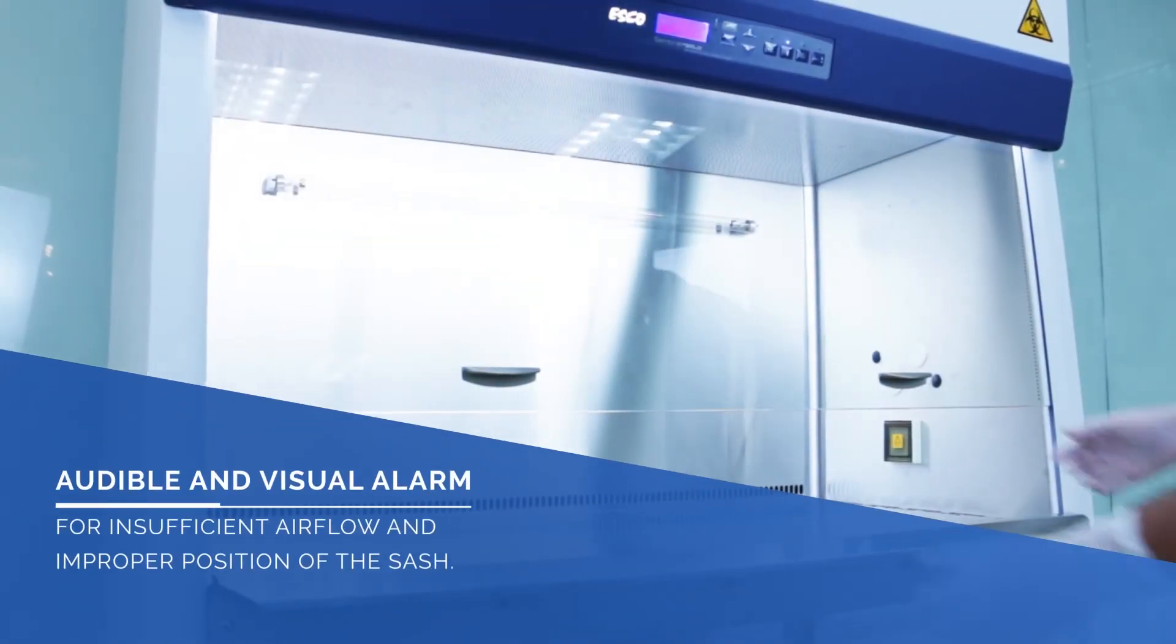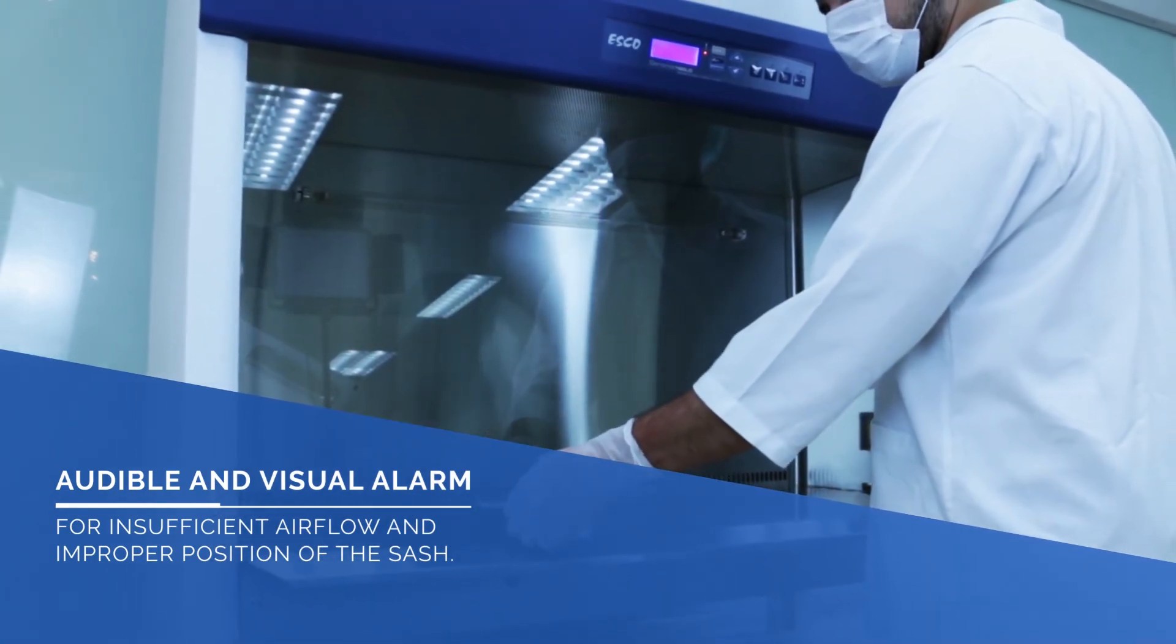There are audible and visual alarms in case of insufficient airflow and improper position of the sash.